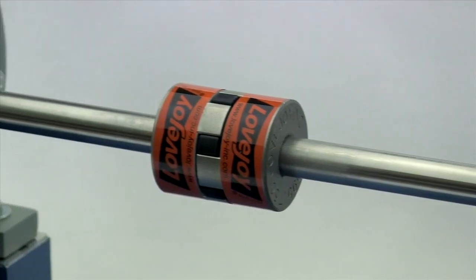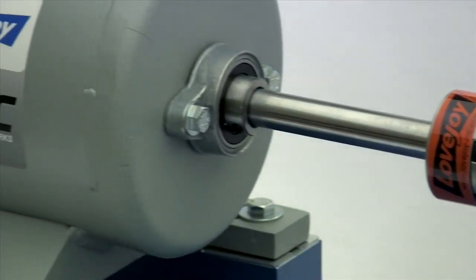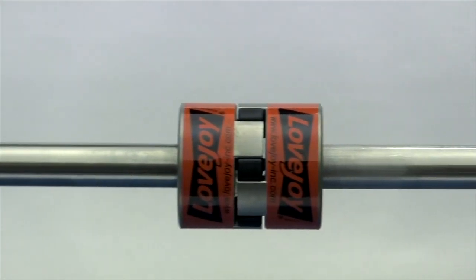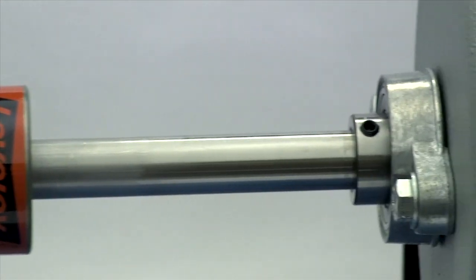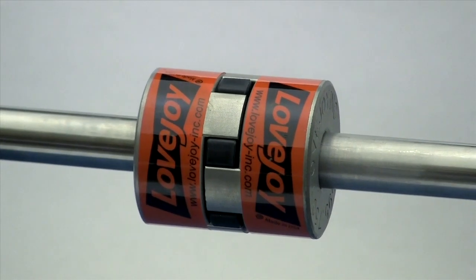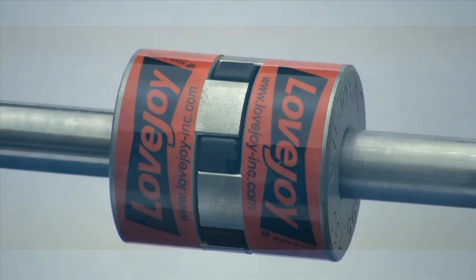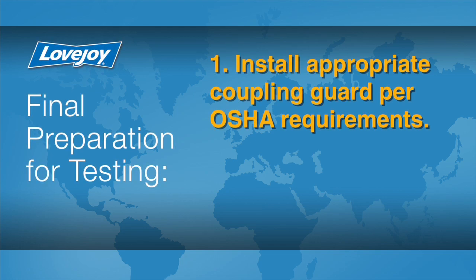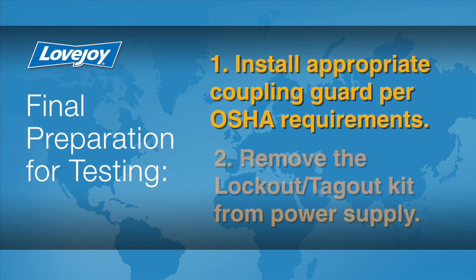When the installation is complete and the equipment is aligned to within the specification, remove the tooling and materials away from the shafting and coupling. Double check tightness for all set screws with a calibrated torque wrench, then prepare for testing. Install the appropriate coupling guard per OSHA requirements and remove the lockout tagout kit from the power supply.